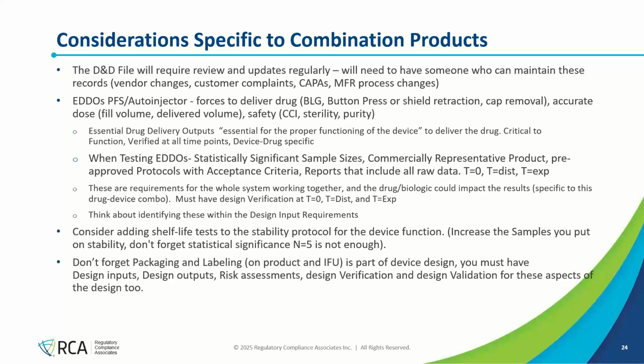For things like a prefilled syringe, well, actually, let's back it up. Think about this as the forces it takes to deliver this. So break loose and glide, button press forces, shield retraction forces, cap removal forces. Those are usually EDDOs. Any requirements that help you define an accurate dose getting delivered, fill volume, delivered volume, etc. And then think safety. So CCI, container closure integrity, sterility, purity. Those would also be EDDOs, since the combination product that the drug or pharmaceutical is contained within helps to or participates in the maintenance of sterility, purity of the product, etc.